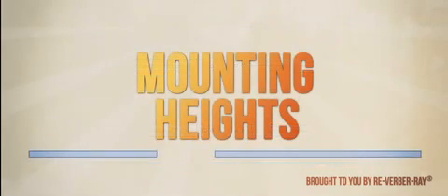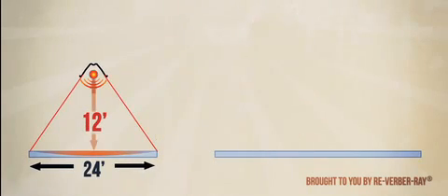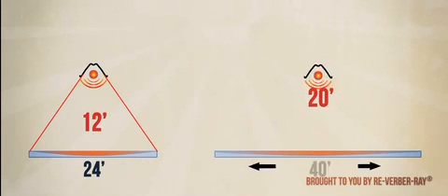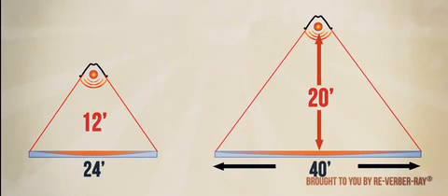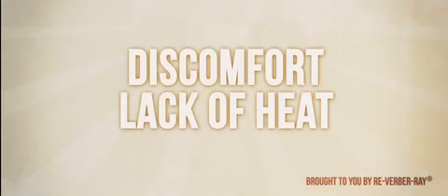While mounting heights are not mandatory to follow, they are one of the most important factors in the selection process as they are directly correlated to the radiant footprint and overall perceived comfort levels. If infrared heaters are mounted too low or too high, they may result in discomfort or a lack of heat.